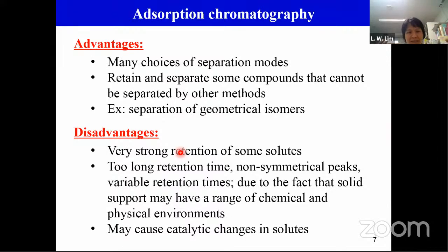Sometimes when you have bad separation, like overlapping, tailing, or fronting, when your peak shape is not good, sometimes at the beginning of this part there's an empty space here. When there's empty space and your sample goes into the column, some broadening will happen here. Even though it's a small part, sometimes it will affect your peak separations.